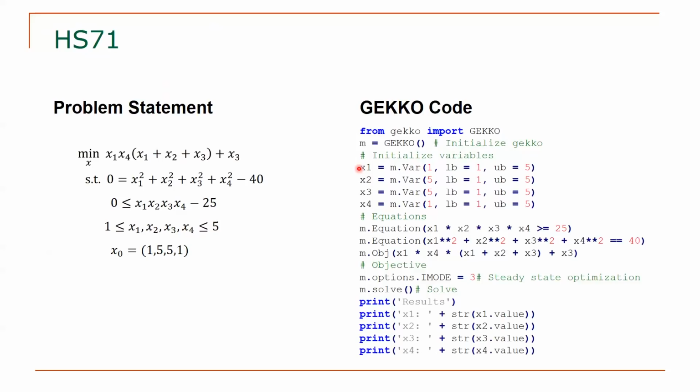Great. And I will add one other thing. There is a tier option that is available for certain MVs and CVs. So you can solve them in multiple phases, where you solve a certain first tier, for example. Let's say you want to try to control properties for a reactor, and then as a next tier, you want to increase production rate, but you don't want to use the MVs from the production rate to affect properties. So it has explicit decoupling that is available.